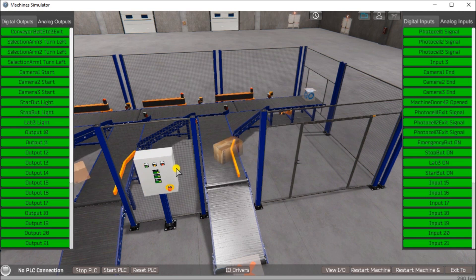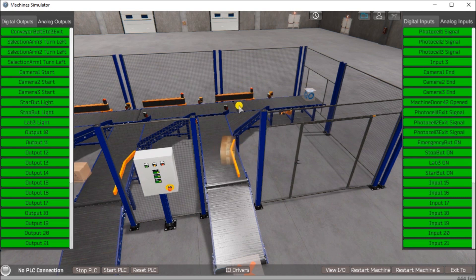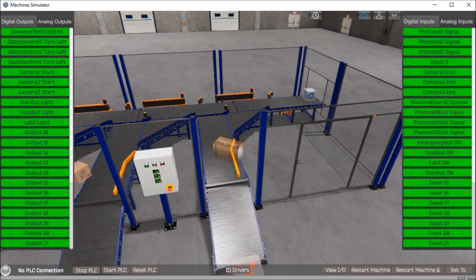Once the door has been corrected, you will then have to hit start again to continue. Looking at the operation, boxes come in, the camera scans the barcode — which will be indicated in red — and if it matches a particular output, it will turn and send the box down that exit conveyor. That is the logical sequence, which is step three — you're going to spend a lot of time in this step defining exactly what has to happen.